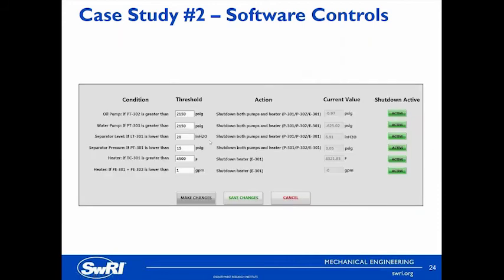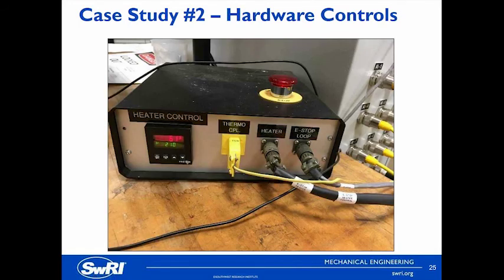This is a screenshot from the control software for this facility. You can see that safety shutdowns are configurable — you can tell if they are active or turn them off, and it shows if they're tripped or untripped. This facility has one separator and two pumps. There are shutdowns for high oil pressure from the oil pump, high pressure from the water pump, and other items like low pressure from the separator and high temperature from the heater. The shutdown configuration shows: if pressure right after the oil pump is greater than 2,150 PSI, the action is to shut down both pumps and the heater. This is nice because we can change these for different setups and it's configurable — we can also turn them on and off as needed. We also have a pressure switch after each pump, wired independently: if those switches activate, they will shut down that pump and also the heater.